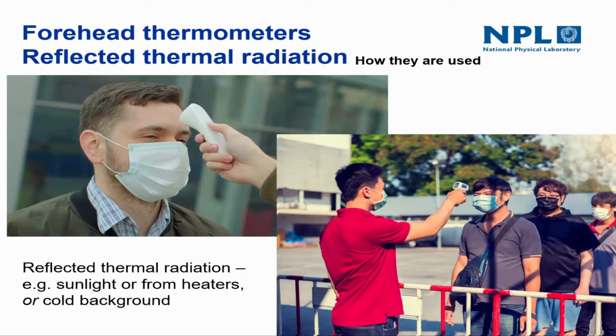And of course, reflected thermal radiation is important. The skin emissivity is quite high, about 0.98. That means about 2% of the thermal radiation that the device measures is reflected from outside.